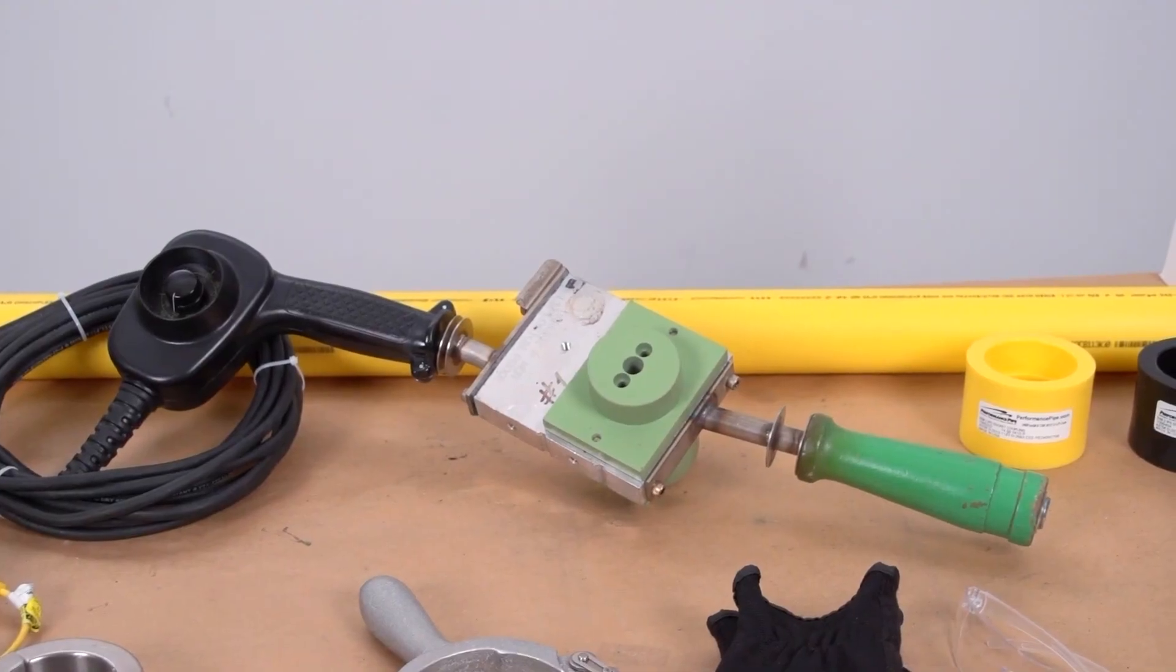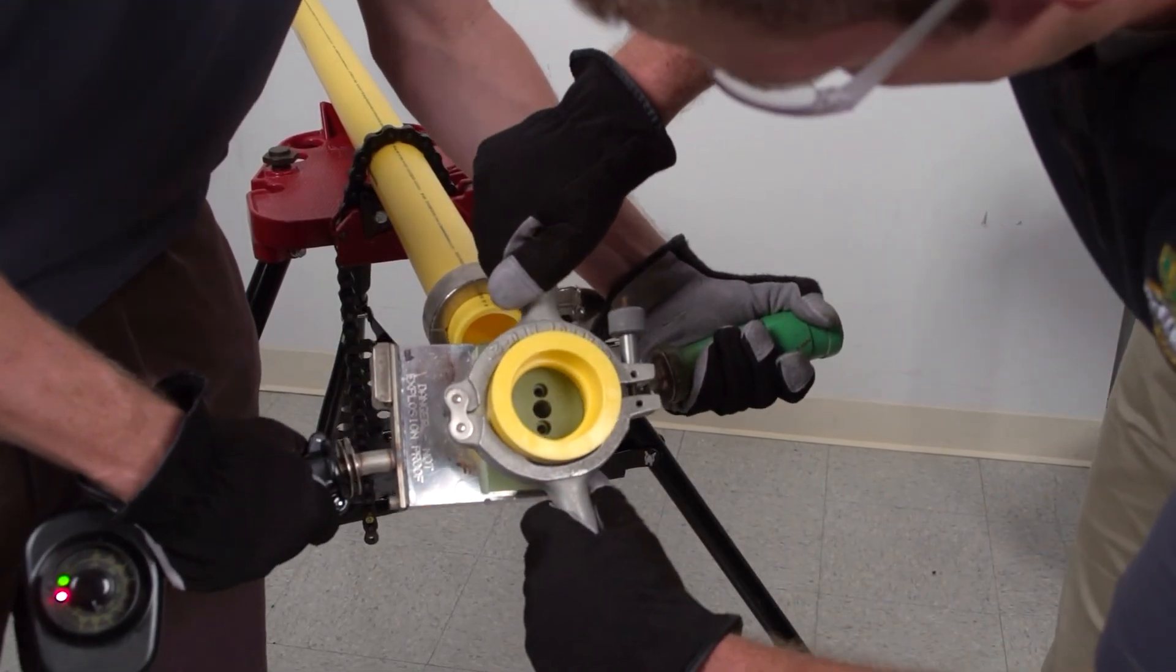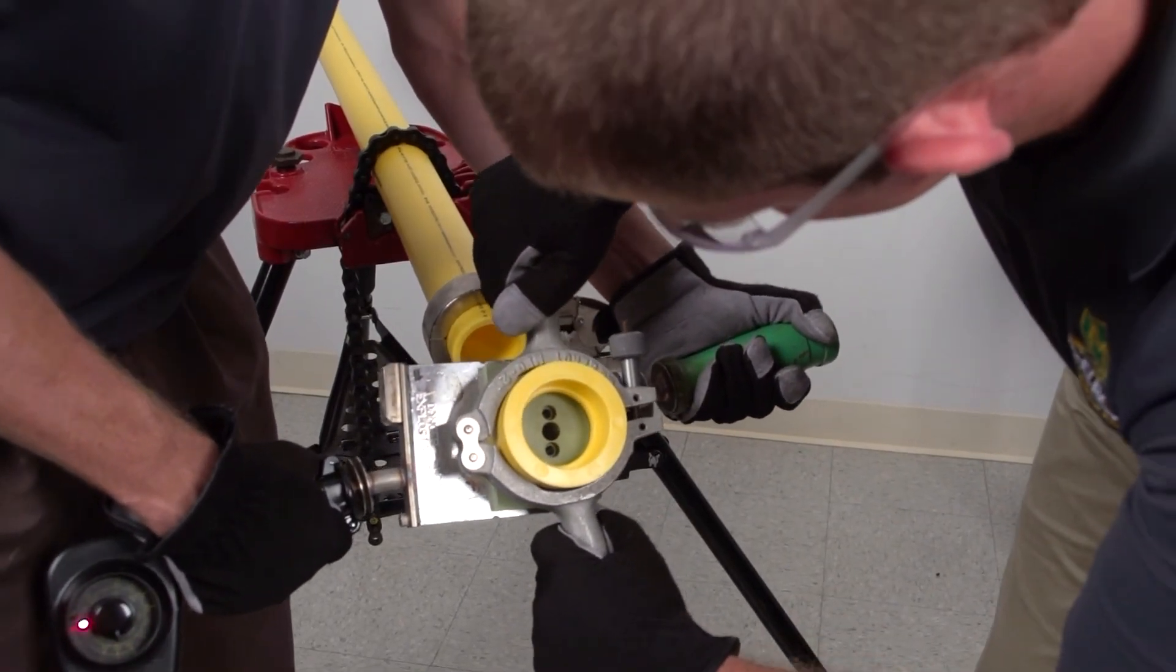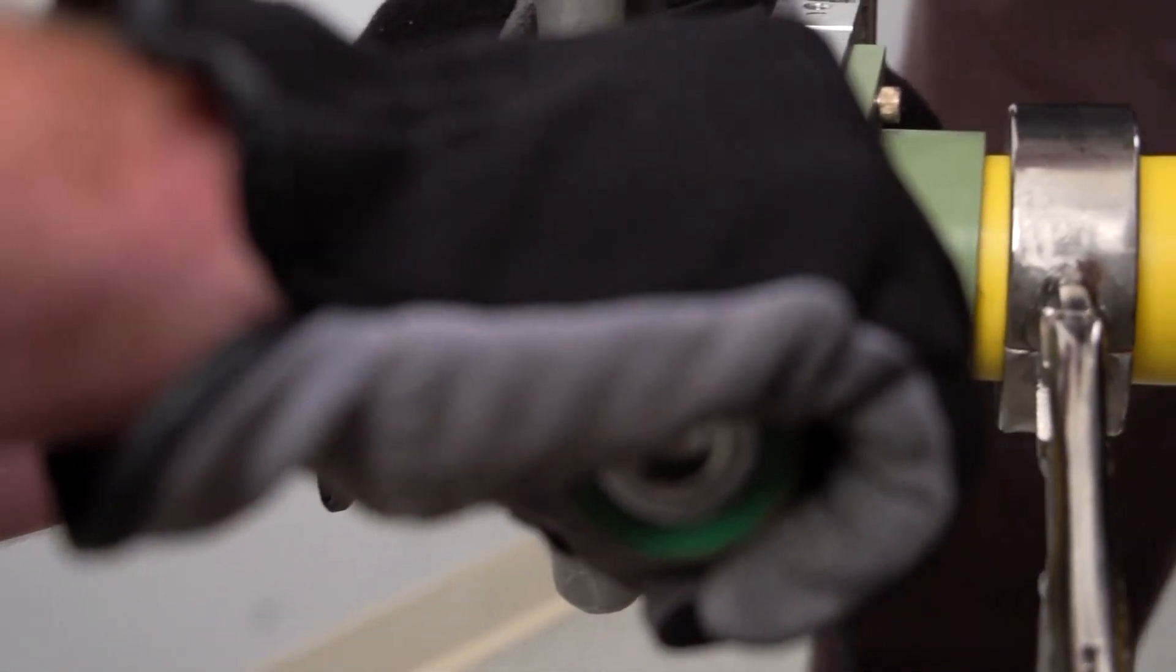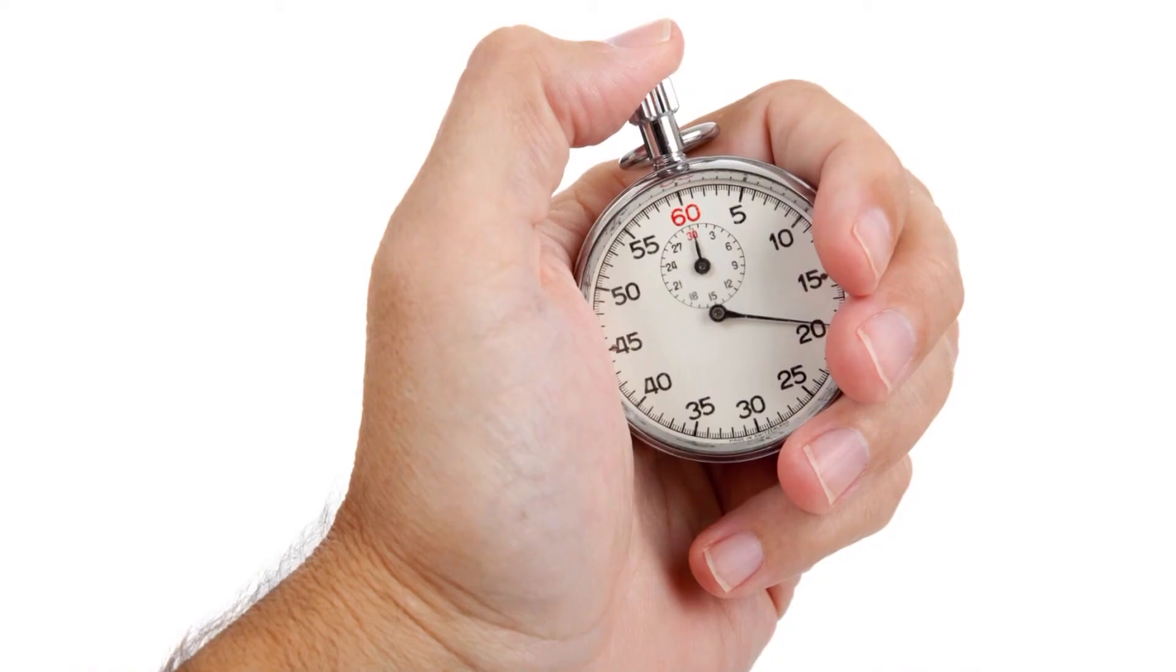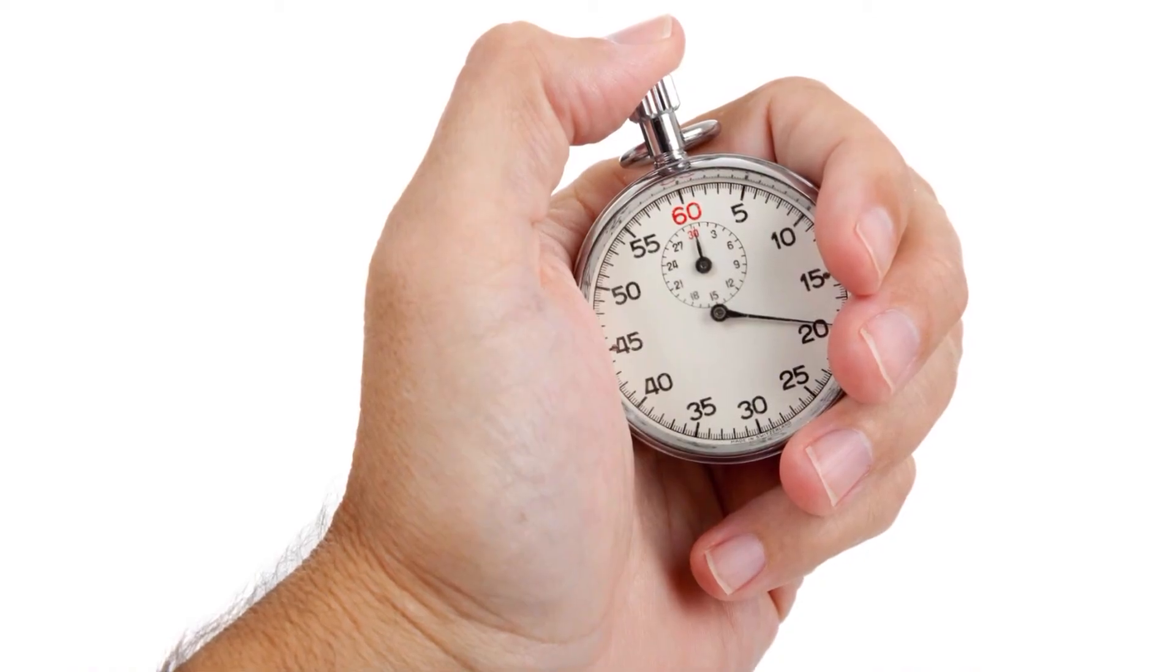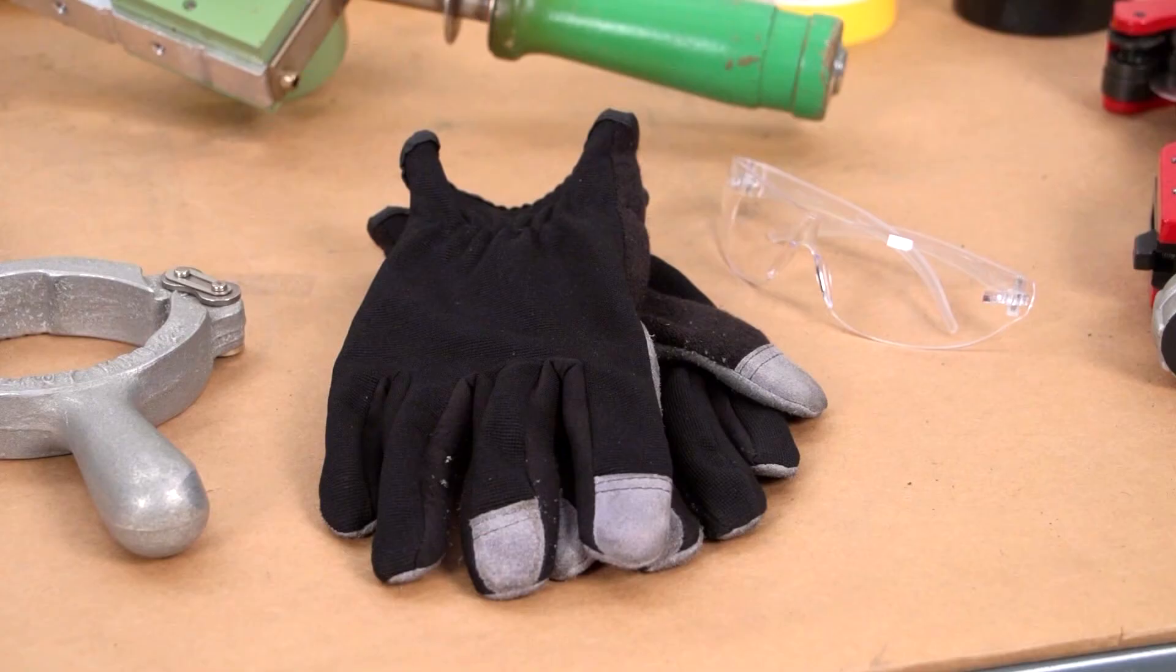A cold ring clamp, a heating tool with male and female socket faces. Heating tool male and female socket faces should meet ASTM F1056 socket fusion tools for use in socket fusion joining polyethylene pipe or tubing and fittings. You'll also need timing equipment such as a watch with a second hand. Holding tools are desirable for 2-inch IPS or larger pipe and fittings. Clean work gloves are suggested.